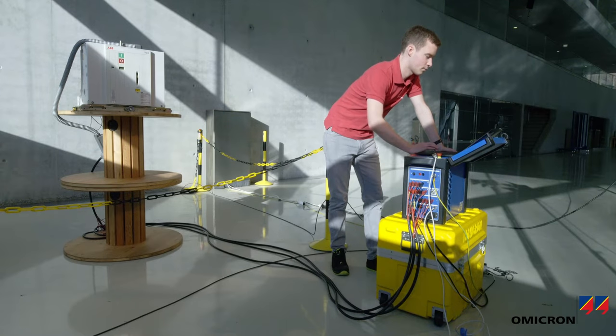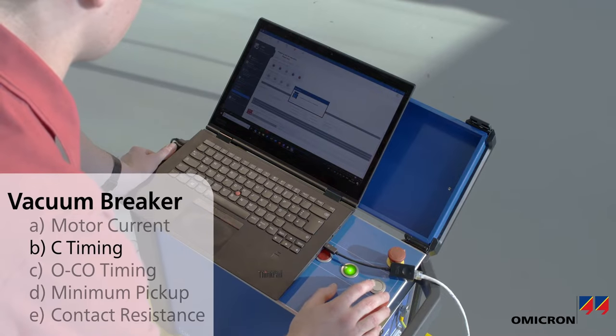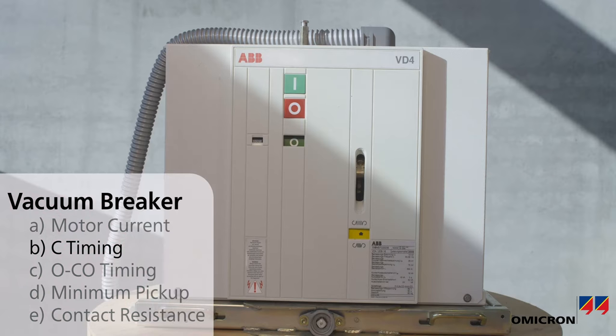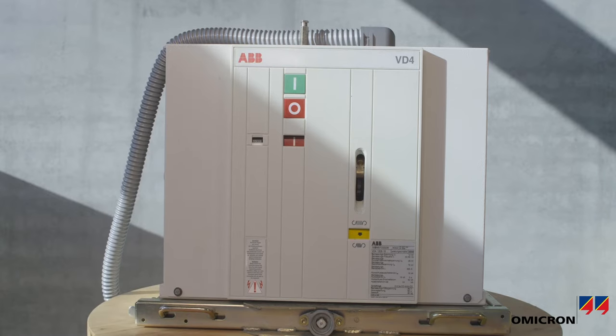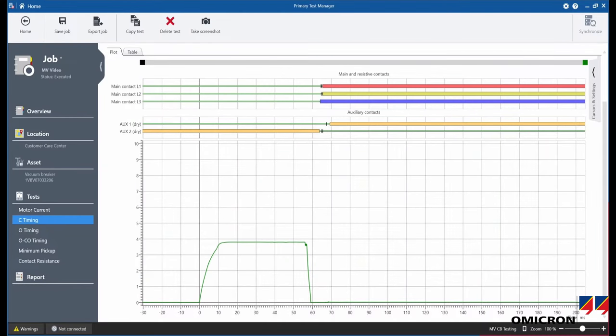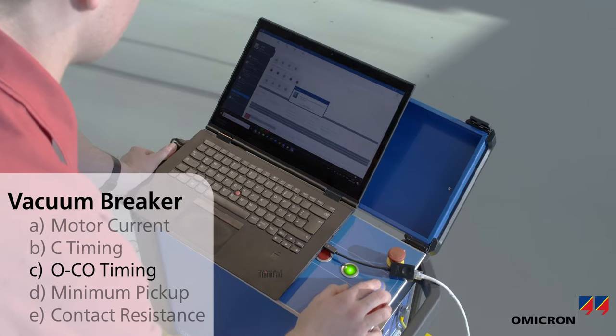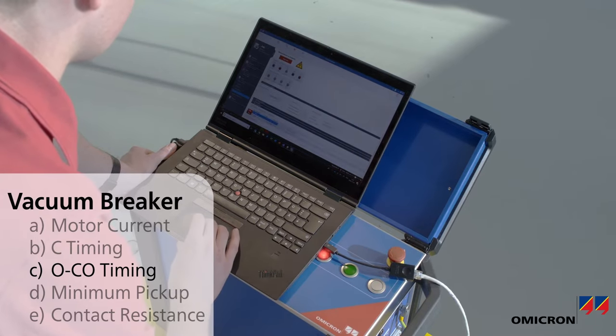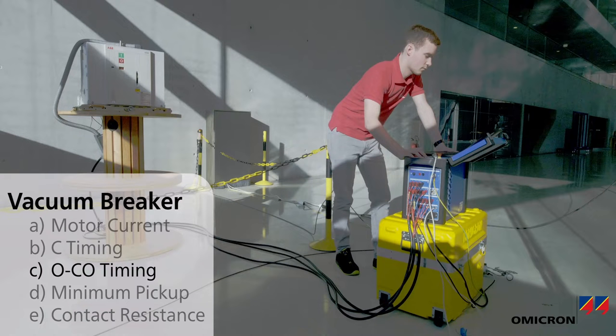Timing tests show the binary states for the open and close operations of the main and auxiliary contacts, as well as the coil currents. CIBANO 500 also allows you to test more complex sequences in order to check the reclosing function of the breakers.